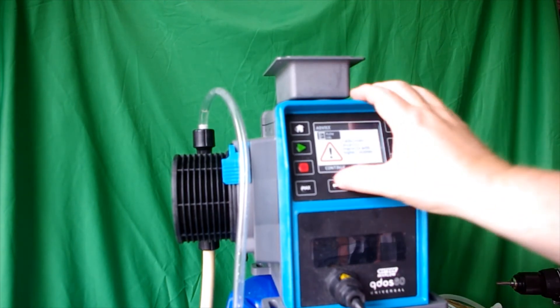And at 60 I stopped the pump. So now it says calibration accuracy improves with higher volumes, we're okay, we want to continue. So it says on the pump that I pumped 103.3 milliliters. I checked my graduated cylinder and it says no, actually you pumped 110 milliliters in a minute. So I could go and adjust this level to 110 milliliters, that's what my graduated cylinder says. So 110.0, I enter my value.